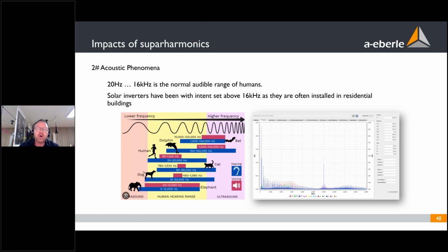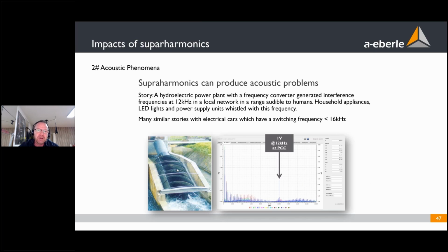But we're getting more and more acoustic problems in our grid. Here in a small village, somebody installed a small hydro power plant, with a frequency converter, depending on the water. And if they install this small power plant in the small village, we always see 12 kilohertz. The 12 kilohertz on the voltage, with about 1 volt, will be delivered to all consumers in the low voltage grid till the transformer.